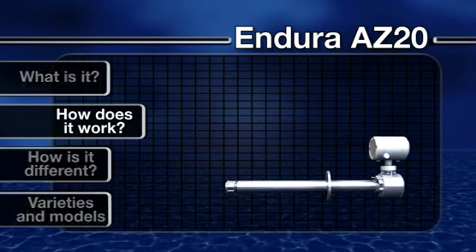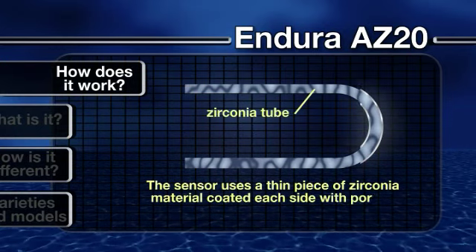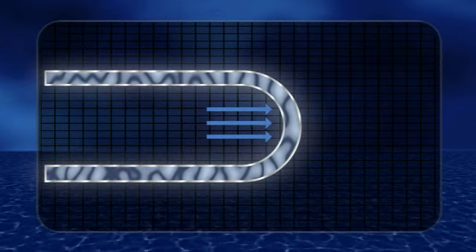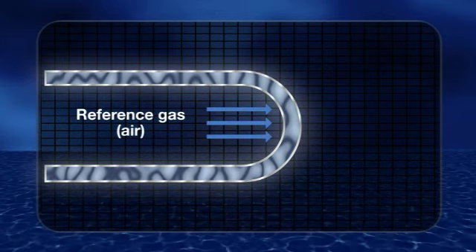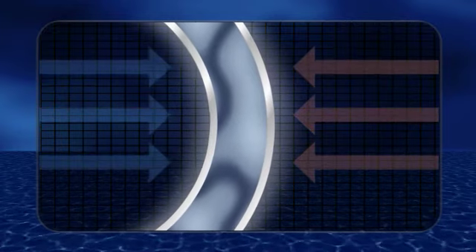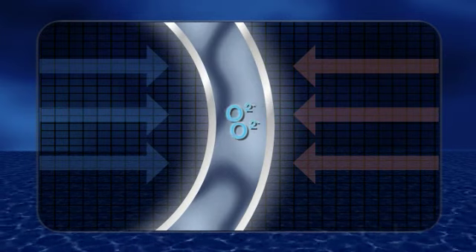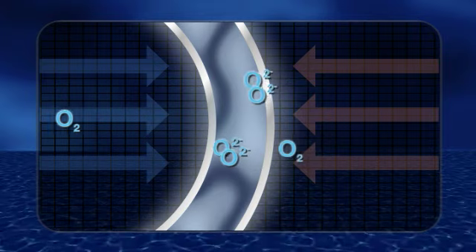How does it work? The Endura AZ-20 sensor uses a thin piece of zirconia material coated on each side with porous platinum. Air is supplied to one side as a reference gas to provide a constant oxygen concentration. The process gas is presented to the opposite side. The platinum acts as a catalyst in the presence of oxygen gas, converting molecular oxygen to oxygen ions. These ions can then migrate through the solid zirconia electrolyte.